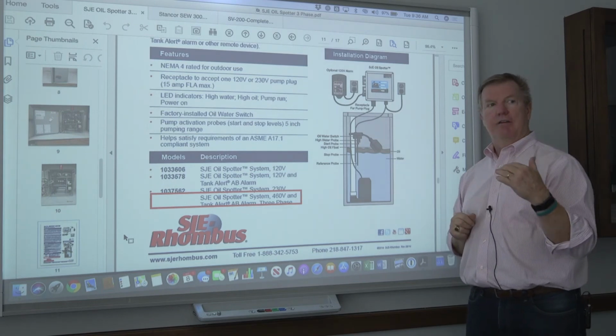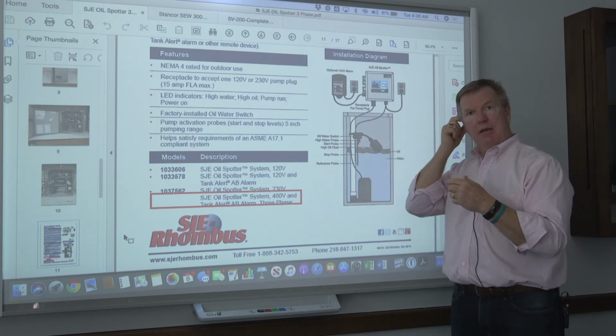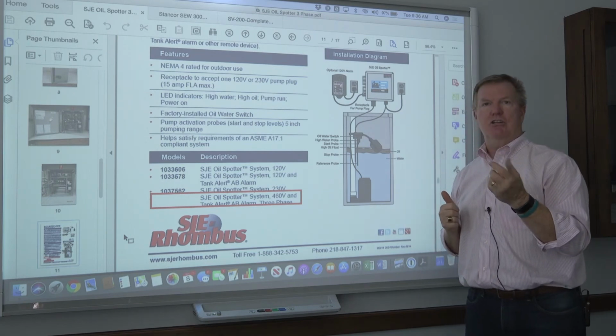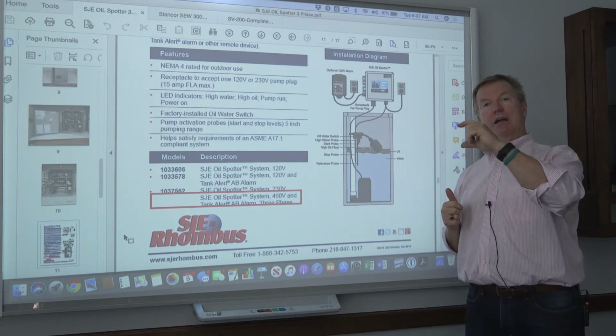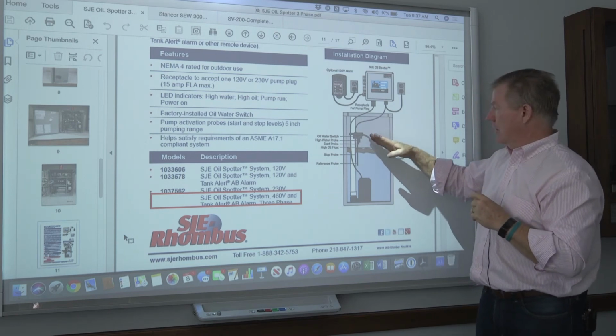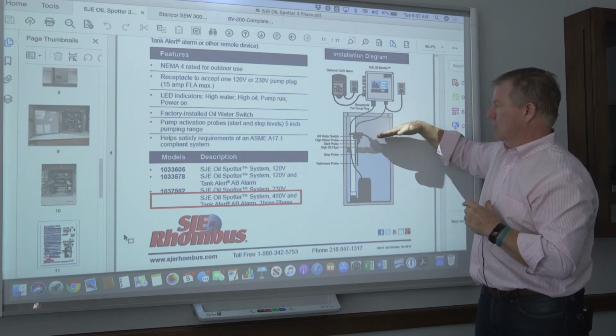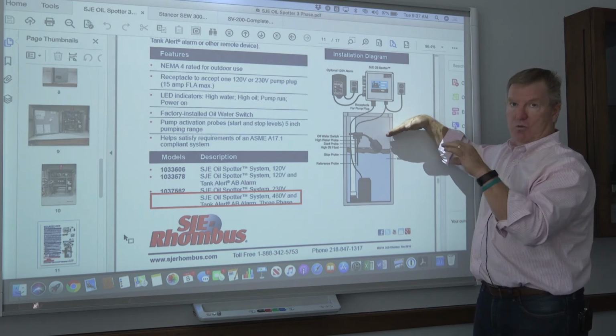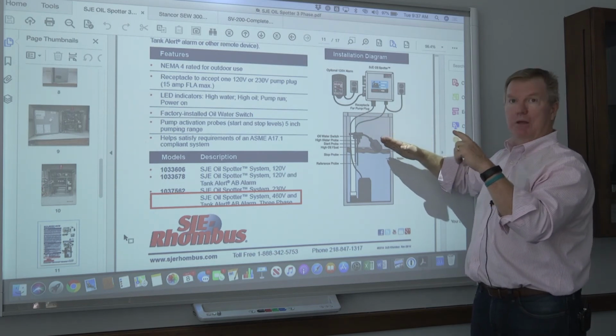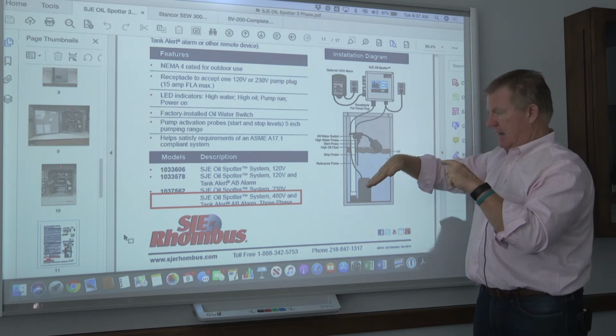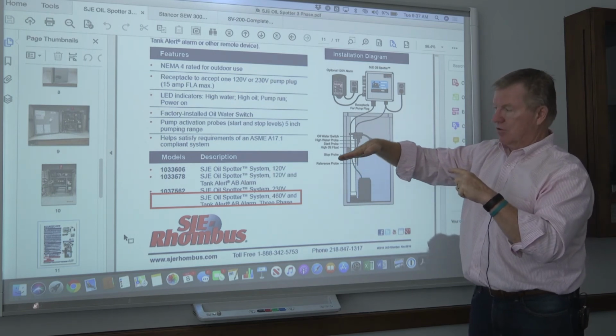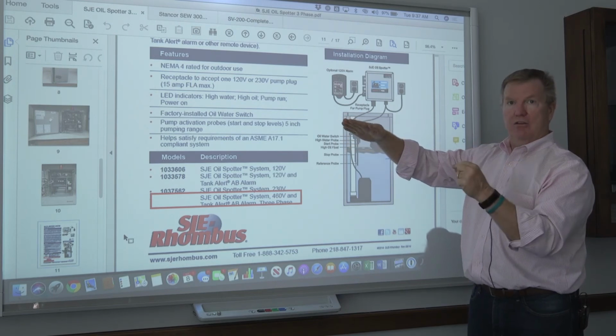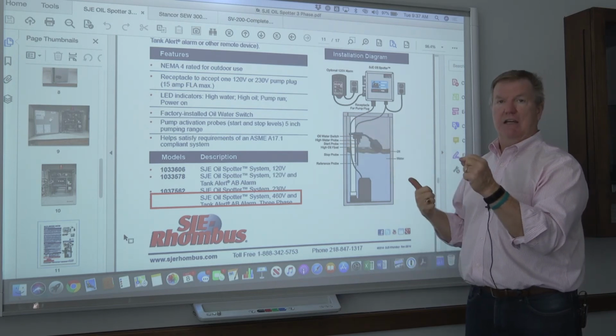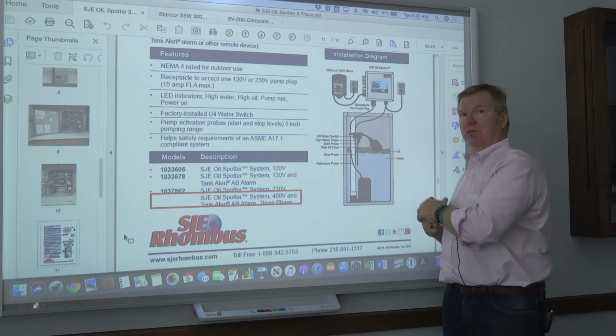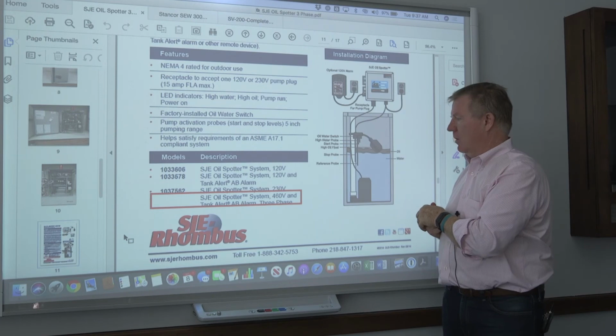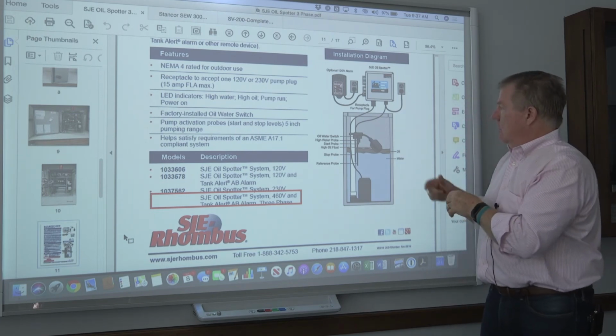And you will not have the float switch on the top. This is like a mercury style or a snap action float switch that is only going to turn on when the level of that float goes above horizontal. So there's a switch in there that's designed to stay open when the float switch is hanging in a downward position, and as soon as that float comes up above horizontal, that's when that switch closes and gives us a contact that says there's an accumulation of oil on top of the water. Okay?